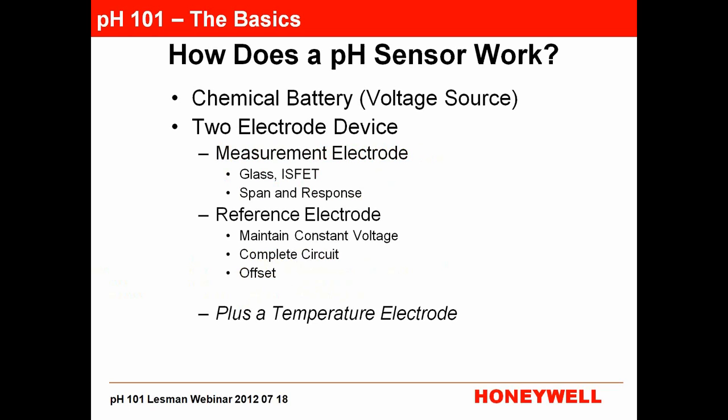Let's talk about how a pH sensor works. A pH sensor is basically a little chemical battery — it's a two-electrode device. You have a measuring electrode and a reference electrode. The measuring electrode is going to be glass — pH-sensitive glass — or it's going to be an ISFET (ion-sensitive field-effect transistor), which is a newer sort of device. The measuring electrode is responsible for the span and response. If a sensor put in a 4-buffer and 7-buffer measures 4.5 and 6.5, that's a short span or low efficiency, and that's related to the glass.